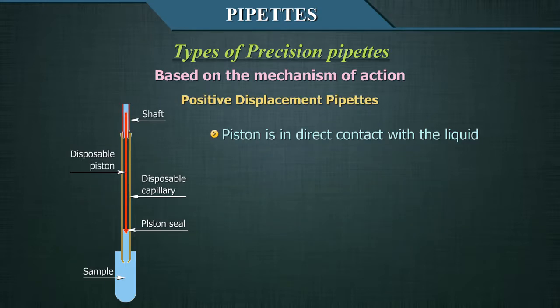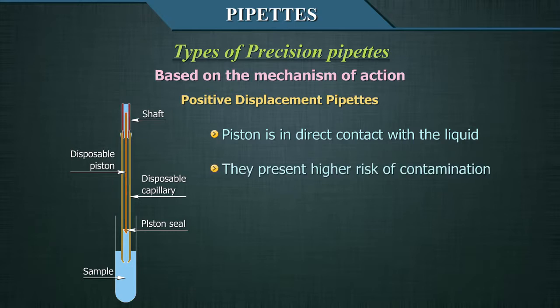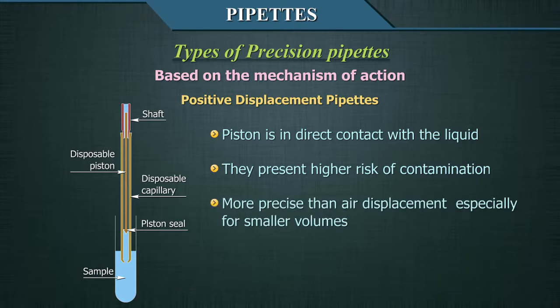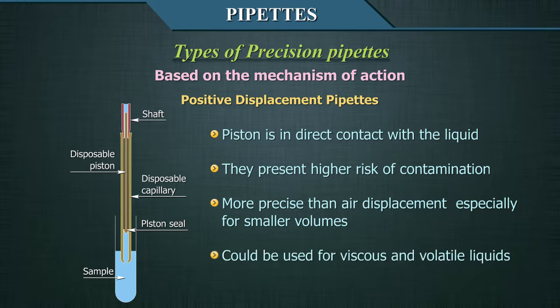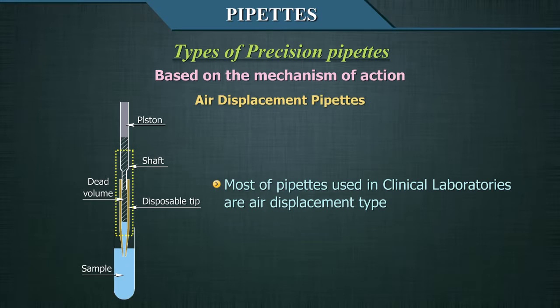Positive displacement pipettes, also called direct displacement pipettes, have the piston in direct contact with the liquid. They present a higher risk of contamination but are more precise than air displacement pipettes, especially for small volumes, and can be used for viscous and volatile liquids. Most pipettes used in the clinical laboratory are the air displacement type.